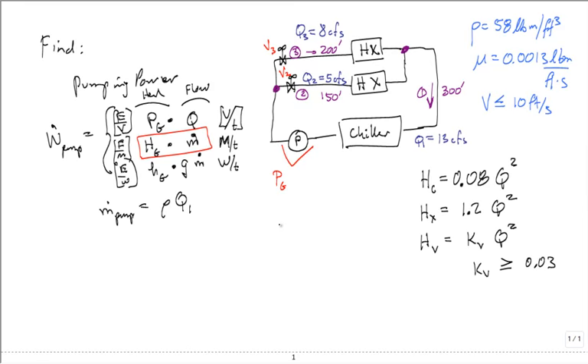Let's do this in Excel. Before jumping there, I'll probably do something like Hardy Cross — but it's not Hardy Cross exactly. I'll have a loop, and for things to be balanced, going around a loop, the sum of head losses must equal the sum of head gains. We'll call that Kirchhoff's head law: around any loop, the sum of heads is zero.